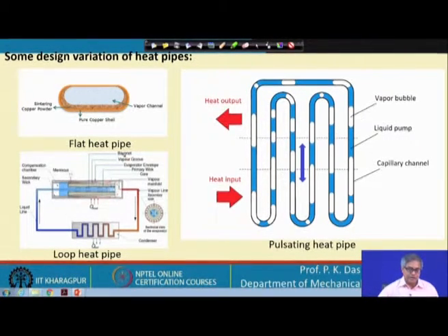This is a structure which has a number of compartments. One, there is a bayonet, then there is vapor groove, evaporator envelope, then primary wick, core, etc. So, one has to go into details, otherwise in a short time it cannot be described. But what we can see basically is that the liquid path and vapor path are different. This is called a loop heat pipe.